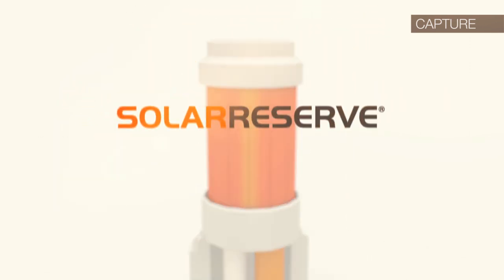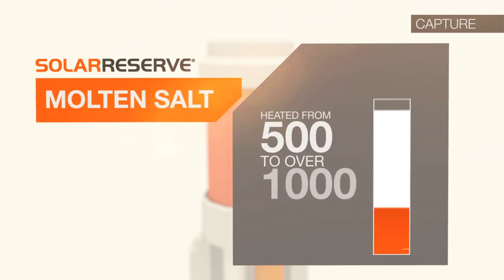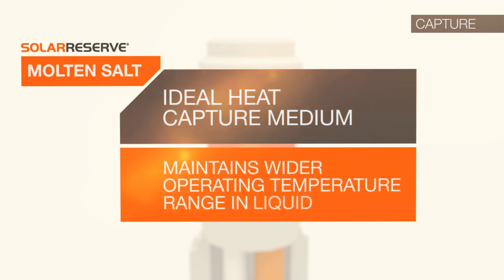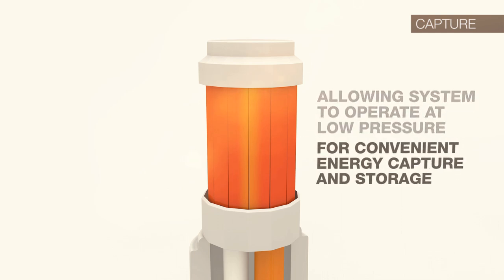In Solar Reserve's technology, the fluid utilized is molten salt which is heated from 500 to over 1,000 degrees Fahrenheit. Molten salt is an ideal heat capture medium because it maintains a wider operating temperature range in liquid state, allowing the system to operate at low pressure for superior and safe energy capture and storage.